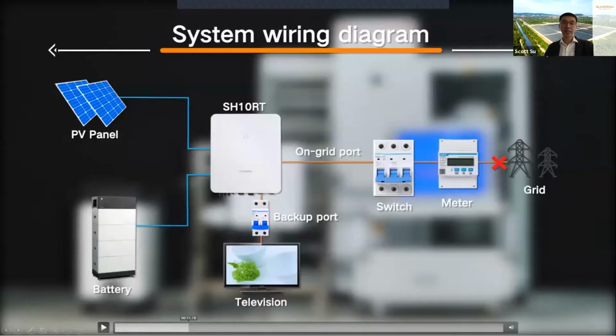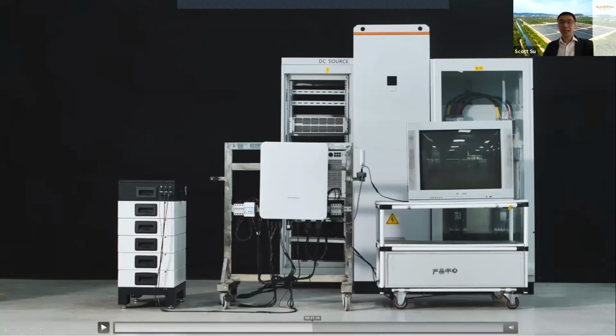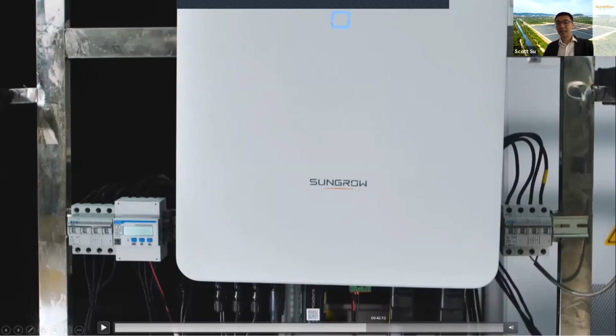Okay, it's done. I go back. So regarding this system diagram, you can see the backup circuit has the television. It's a very old television, and the hybrid inverters. This hybrid inverter connects the PV arrays and the batteries. And here is the main AC circuit. And the engineer, this guy, switched off this main AC circuit. This can simulate the grid is faulty, but you can see the television can still work without any power blackout.